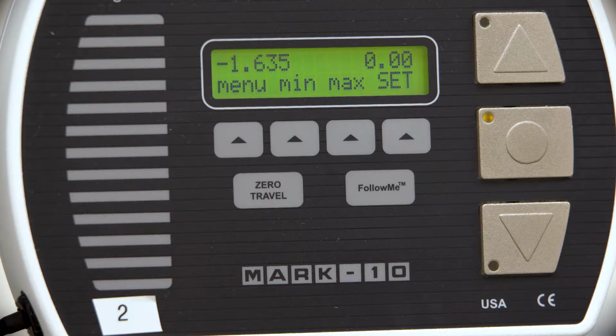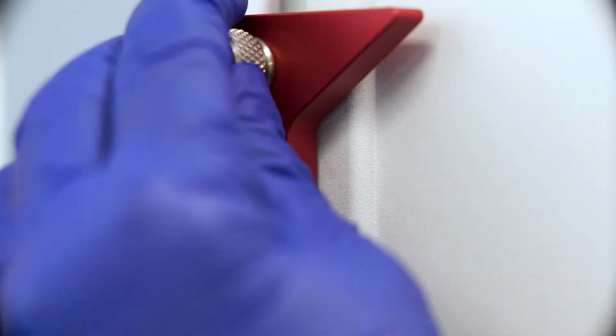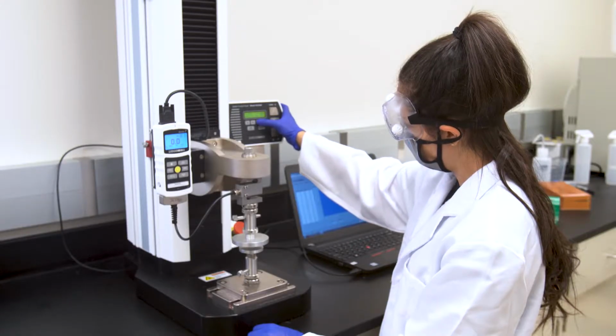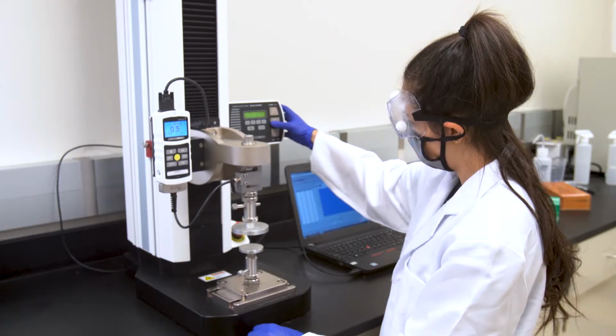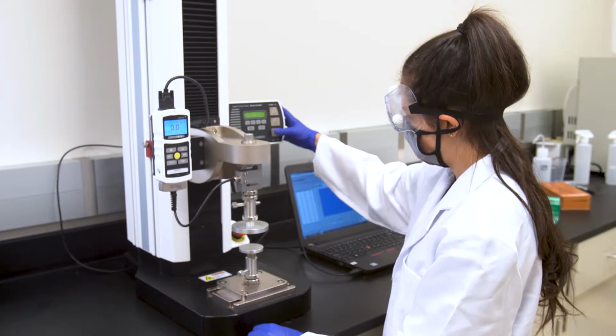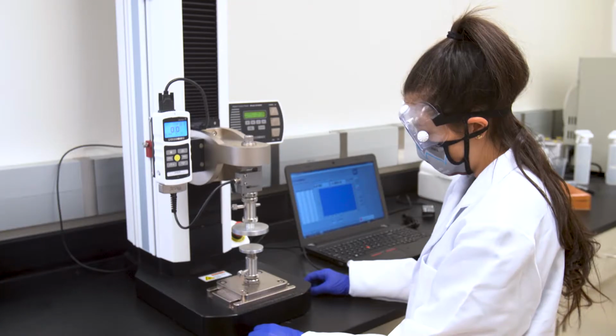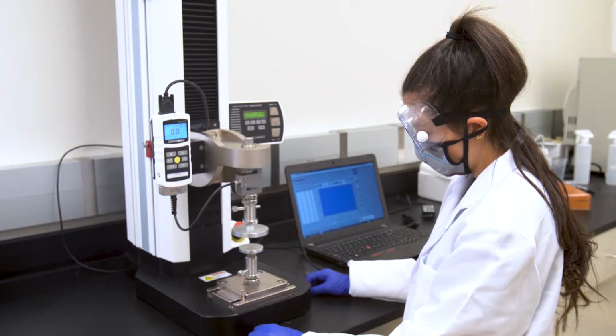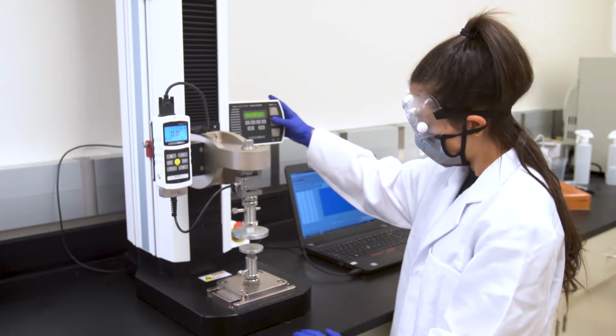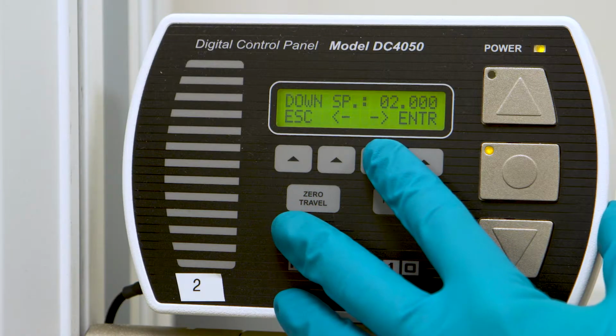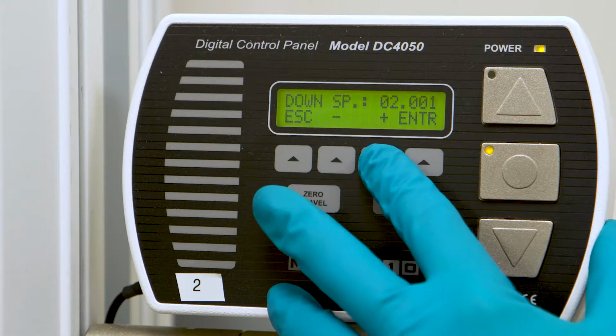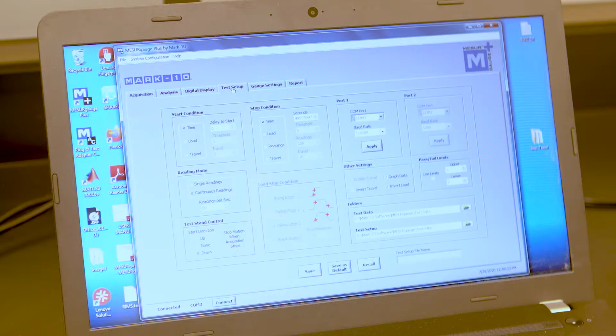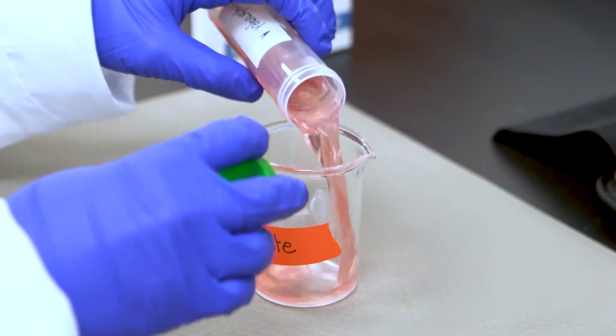While observing the control panel, slowly bring the lower limit stop until you observe the lower limit trigger. Tighten the thumb screw. Verify the setting by bringing the grip up, then slowly driving it down again. Be prepared to stop the load frame in the event that the limit switch is not set properly. When preparing for a compression tensile test, make sure you have an understanding of how to set the appropriate speeds, units, and that the software is functional on the associated computer.